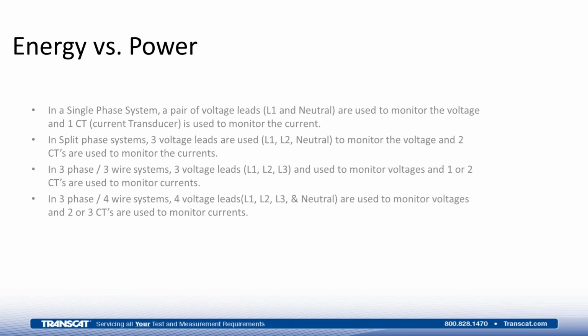Now, our electrical system could be thought of in three different primary modes. There is what is referred to as a single-phase load. A single-phase load would be something like a light in your facility. And in order to monitor that light, you would need a pair of voltage leads that would connect up to both sides of that wire that's going to the lamp. And that would be used to monitor the voltage.